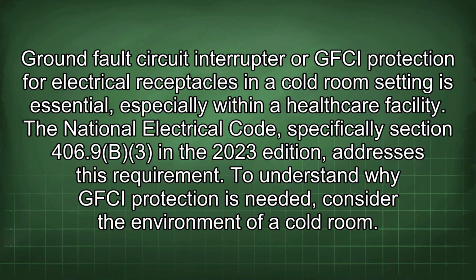Ground fault circuit interrupter, or GFCI, protection for electrical receptacles in a cold room setting is essential, especially within a healthcare facility. The National Electrical Code, specifically Section 406.9(B)(3) in the 2023 edition, addresses this requirement. To understand why GFCI protection is needed, consider the environment of a cold room.